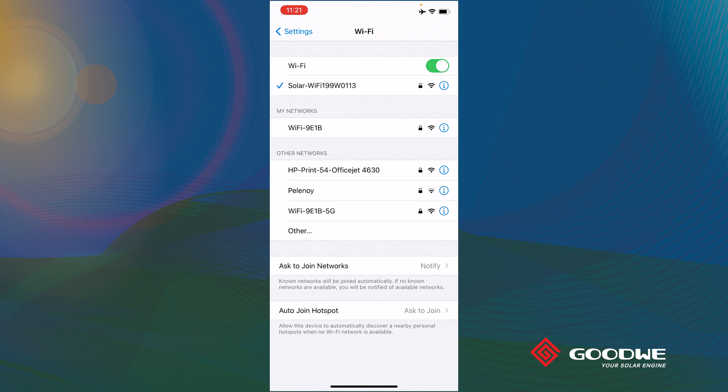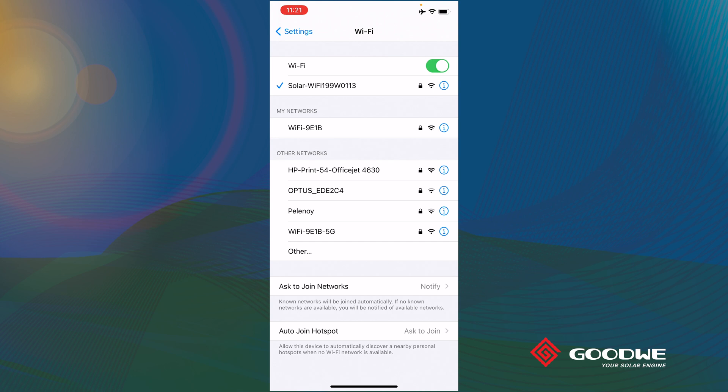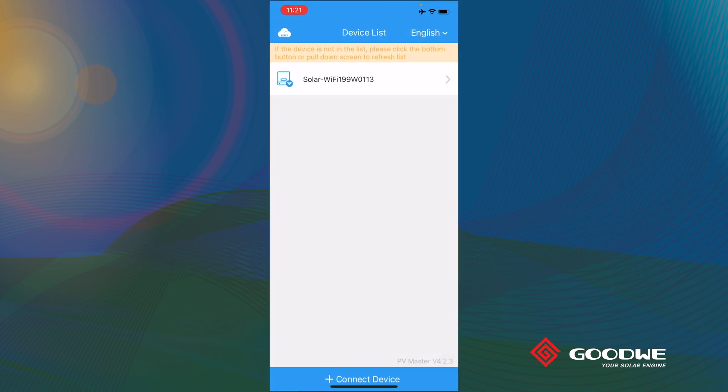Today we are going to use a smartphone to demo how to commission a Goodwe Hybrid Ready EH inverter. If you have the battery active code, this app also allows you to activate the battery function. First, connect your mobile to the solar Wi-Fi coming from the inverter. Then open the PV Master app, select the inverter you are going to use, and give the app a few seconds — it will show you the operation data collected from that inverter.